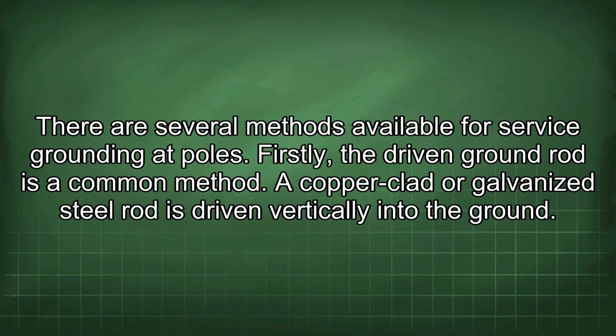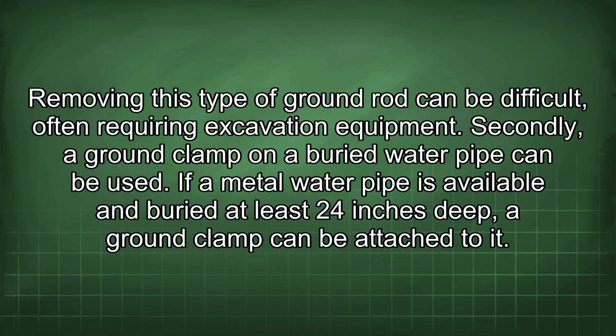There are several methods available for service grounding at poles. Firstly, the driven ground rod is a common method. A copper-clad or galvanized steel rod is driven vertically into the ground. Removing this type of ground rod can be difficult, often requiring excavation equipment.